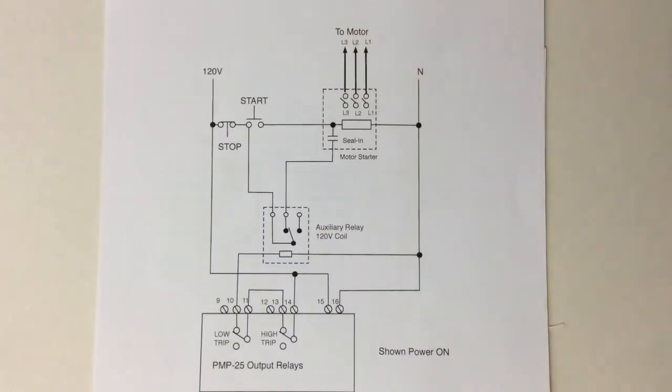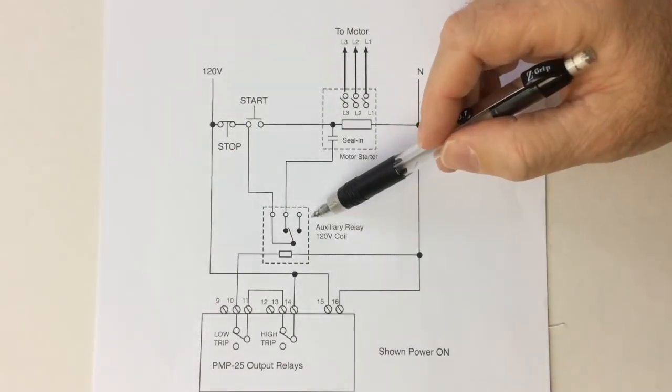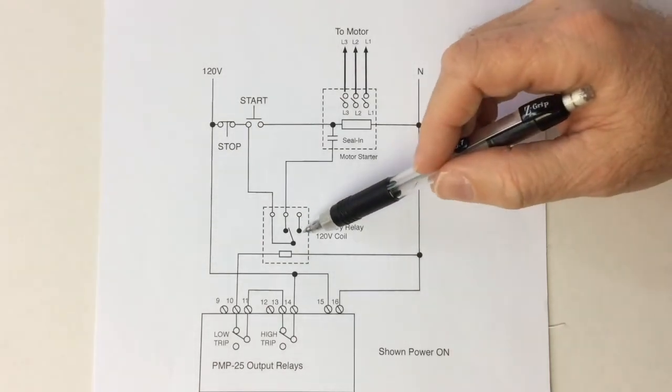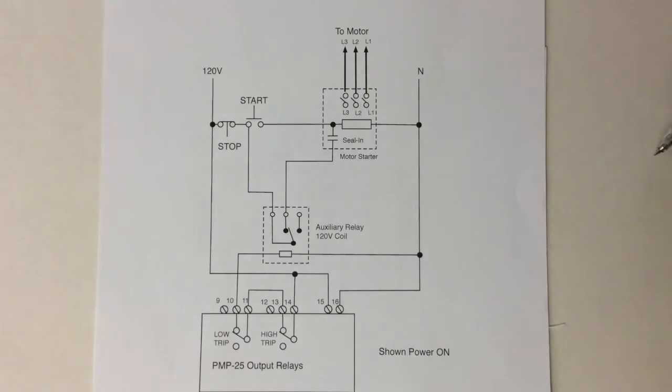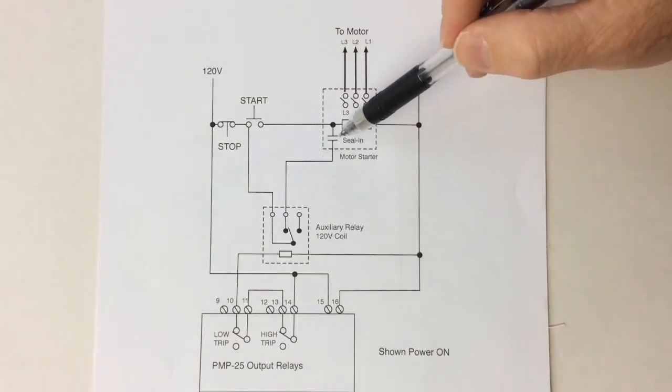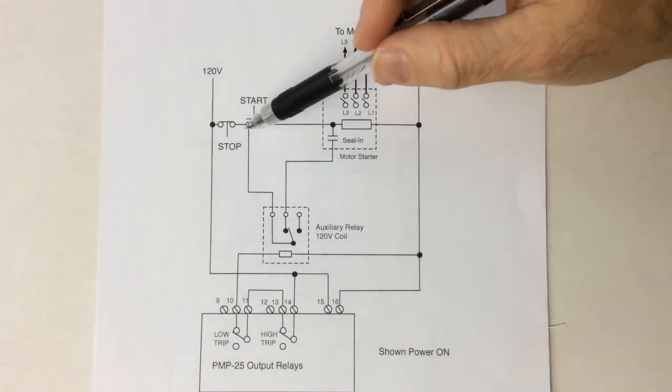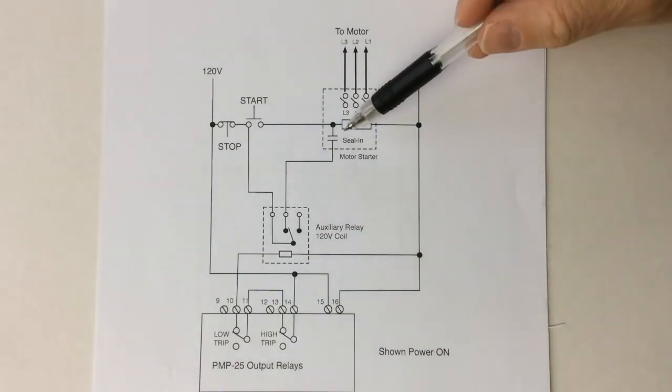This diagram shows an auxiliary relay controlled by the PMP25 and connected to the stop circuit. The contacts of this relay are rated for the larger motor starter. The PMP25 holds the relay coil energized and a normally open contact is held closed in series with the seal-in. When the start switch is closed, the starter coil is held on by the seal-in to run the motor. If either the stop switch or the PMP25 contacts open, the motor shuts down and is held off by the seal-in.